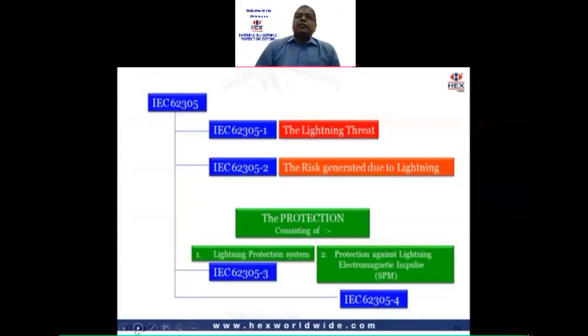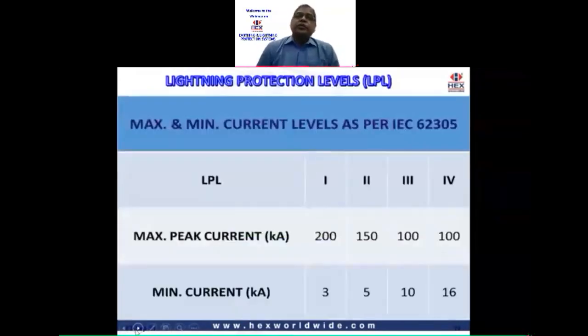Both standards have classified lightning protection into four levels, that is levels 1, 2, 3, and 4. These four levels are defined by the intensity of the lightning current in the thunderstorm. The number of thunderstorm days for any region can be taken from the Tyagi report, which I had shown earlier. Now, the IMD, the Indian Meteorological Department, is in the process of mapping the current lightning intensity all over India. And they should be releasing their report as soon as it is ready.